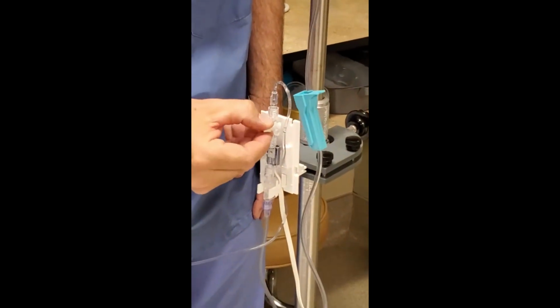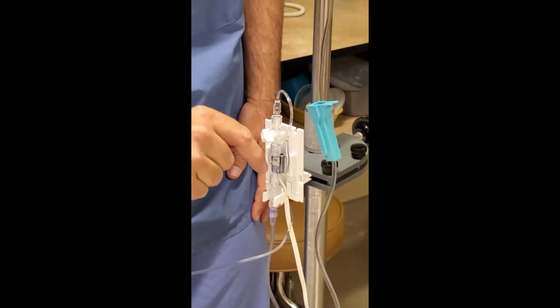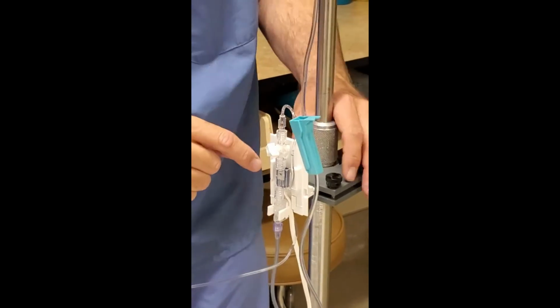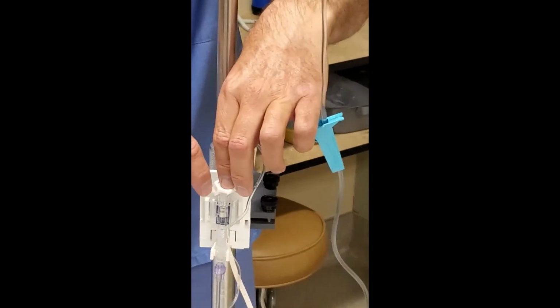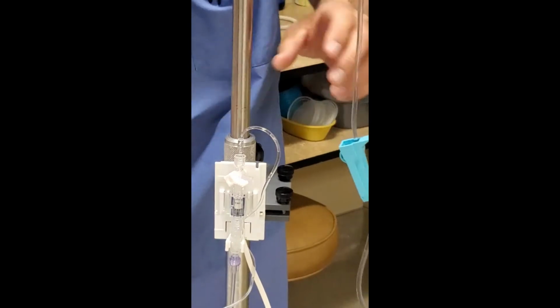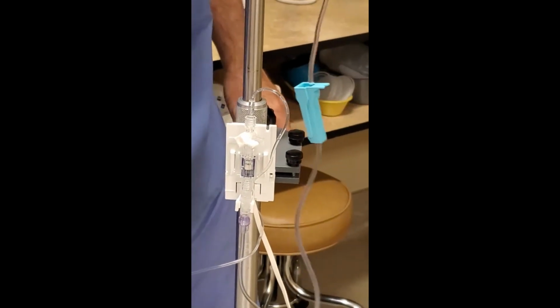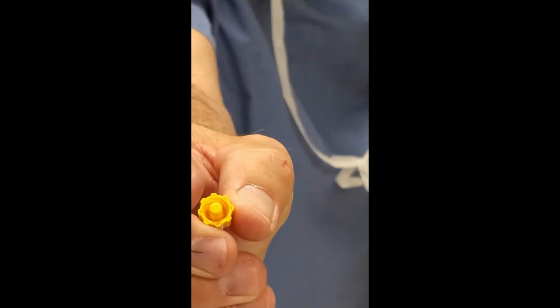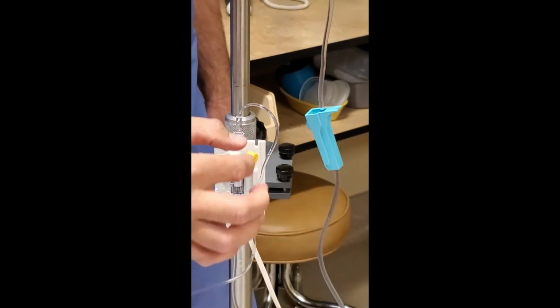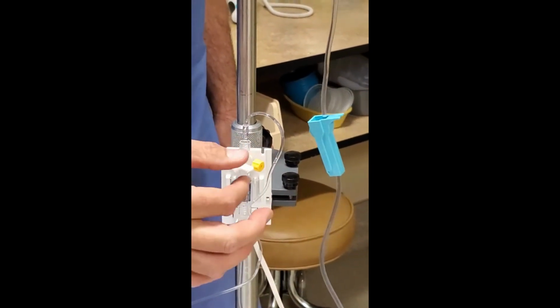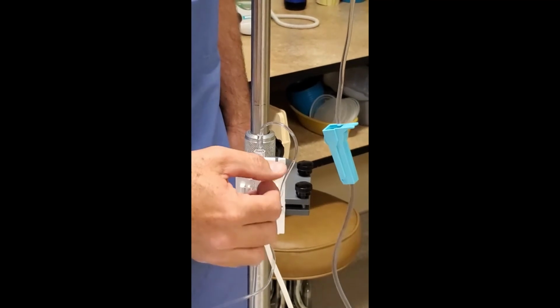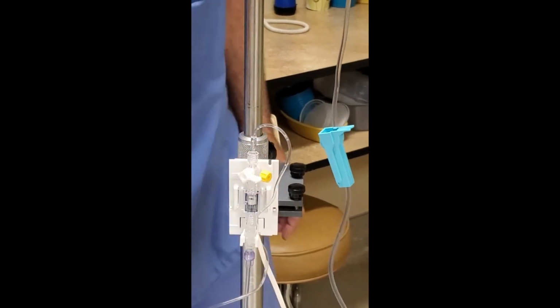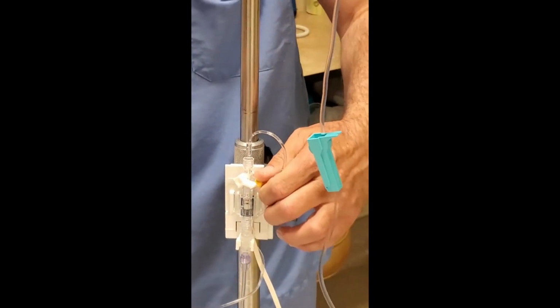That means you turn this back to where fluid can go through here, the pressure can go through the three-way stopcock, in this side, out that side, and down to the transducer. This is a dead-end cap—you want to make sure you have these on with no holes. The priming caps that come with this are white and have holes for priming; you want to change those out for the dead-end cap. Don't crank on it, just barely seat it, because if you crank on it, it'll fuse and you'll never get it off.